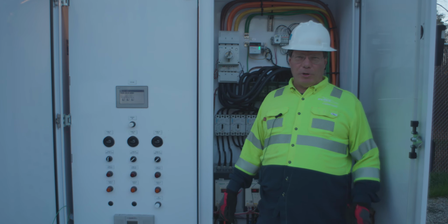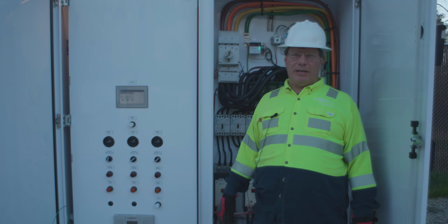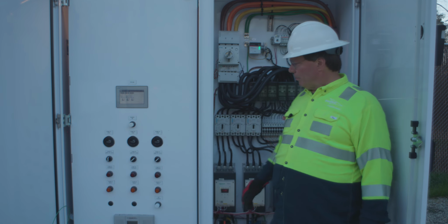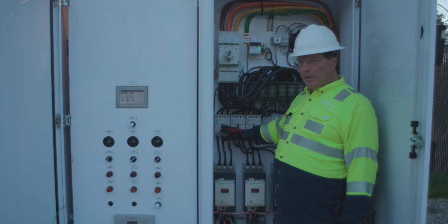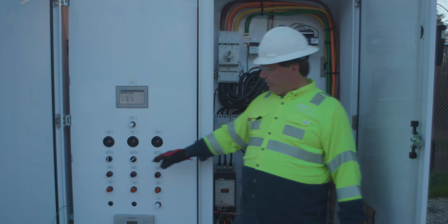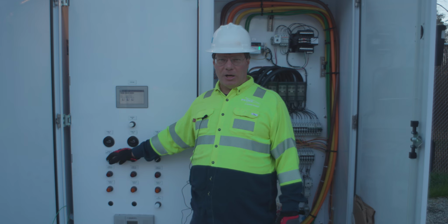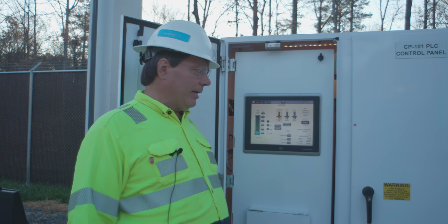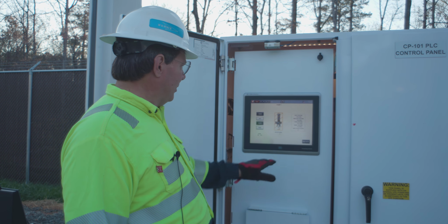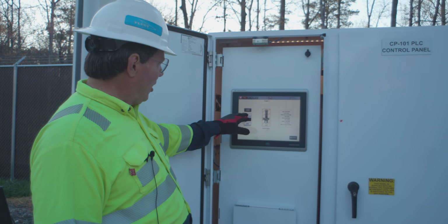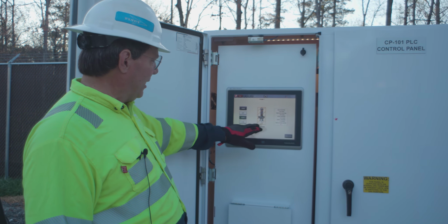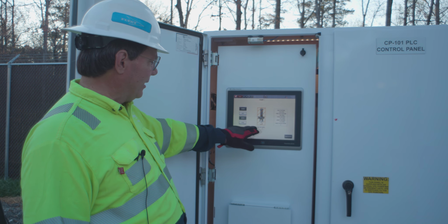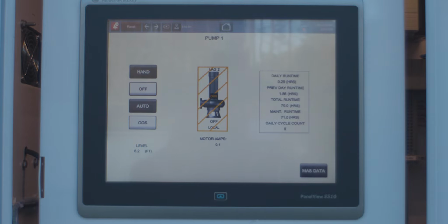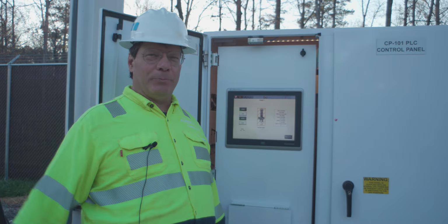Before we go to work on any motor, one of the first things we have to do is make sure that the power's disconnected. For pump one, we're going to turn off pump one's breaker. We're going to turn off the hand-off auto switch. On the PLC, you go to the pump page and you put the pump in off and out of service, and then it'll re-display like this, showing that the pump is off and now no longer available, out of service. Once we do that, then we know we're good to pull the pump.